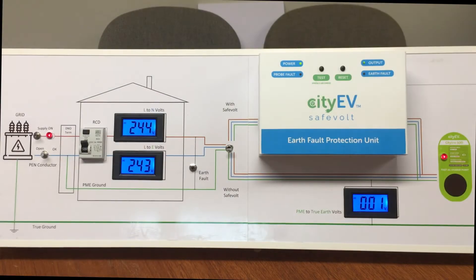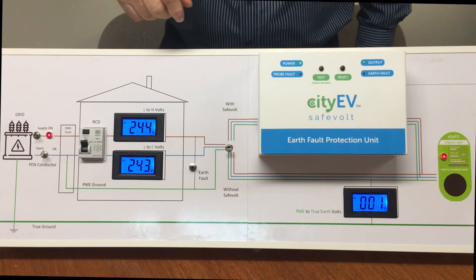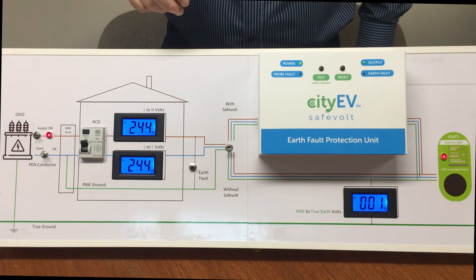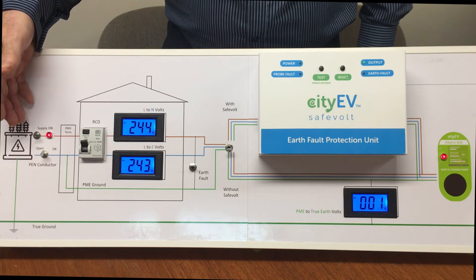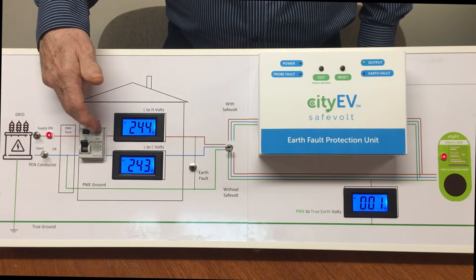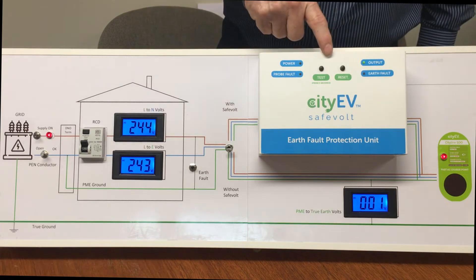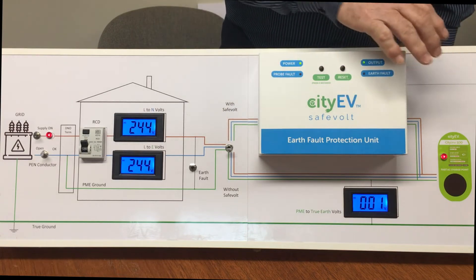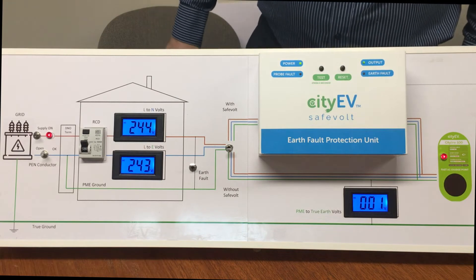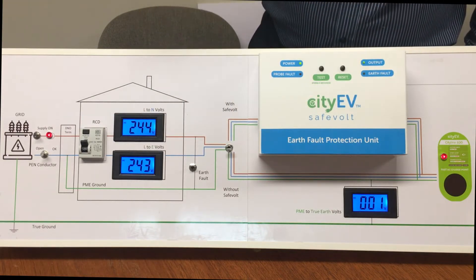A short demonstration now shows the CityEV Safevolt working in a simulated charge point installation environment. This represents a typical single-phase domestic installation, with an incoming supply, the ability to interrupt the supply and simulate a PEN conductor fault, and a master RCD. The CityEV Safevolt can be either included or excluded in the circuit to the charge point. Initially, the Safevolt is not included, with the charge point connected directly to the supply.